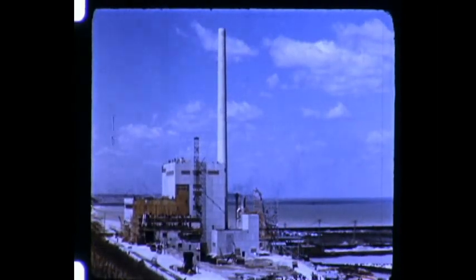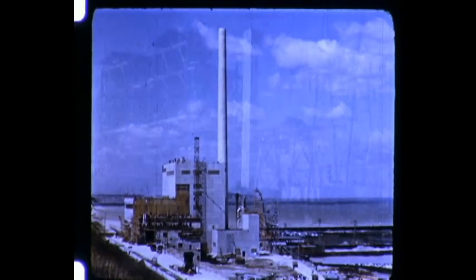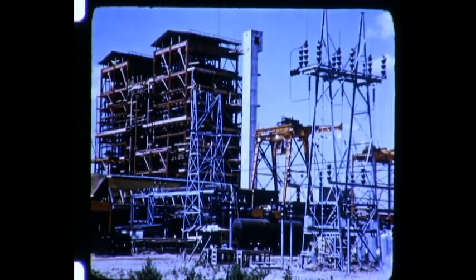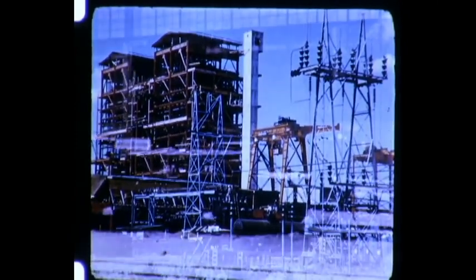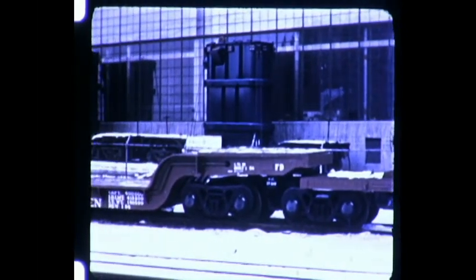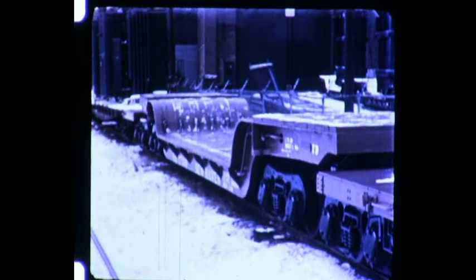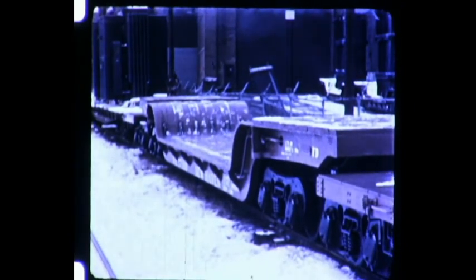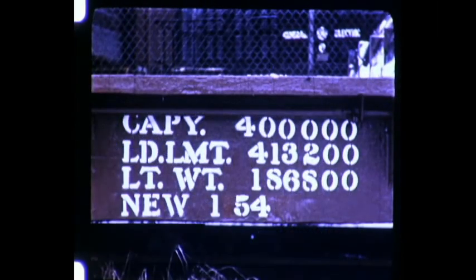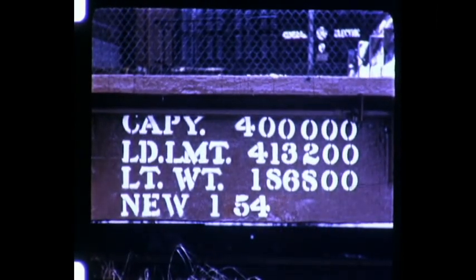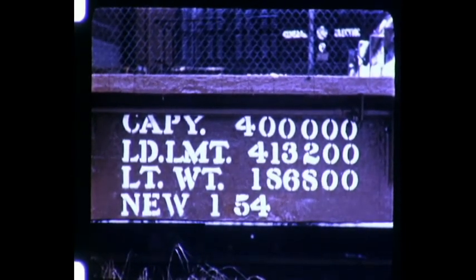But actually, the story of new power plants and new improved equipment is always an unfinished one. For example, only a few months after these scenes at the Delta Station and the Oak Creek Station were recorded, the New Haven Railroad delivered this new drop-frame flat car. Built along specifications of General Electric engineers, this car is a significant step forward in permitting transformers rated as high as 500,000 kVA to be built and shipped upright in a one-piece tank. With a capacity of 400,000 pounds, the new car advances shipping weight by 60,000 pounds over previous limits.